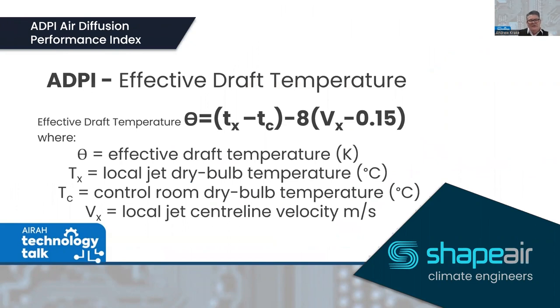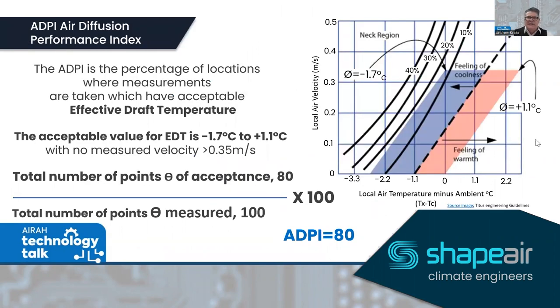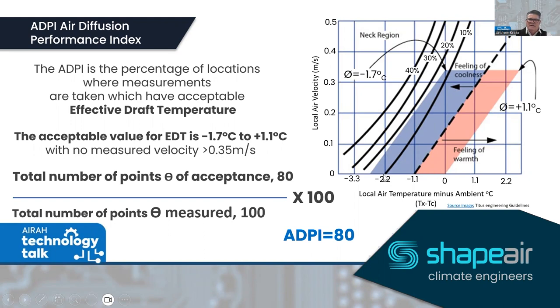The ADPI is an evaluation of effective draft temperature using the formula. In practice: if you had 100 test points and 80 were acceptable, you'd have an ADPI of 80, meaning 80% of the population would be comfortable. The parallelogram on screen shows the range from minus 1.7 to plus 1.1 — the temperature variation we're trying to stay within.